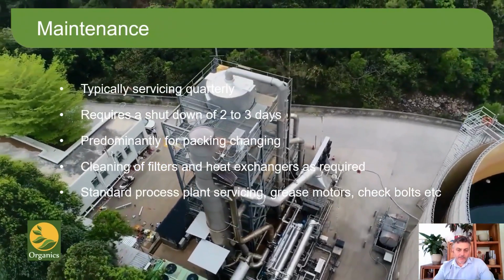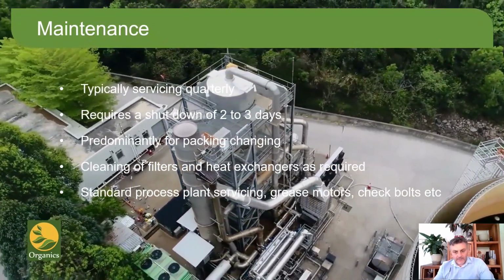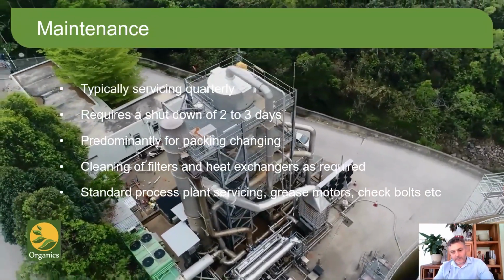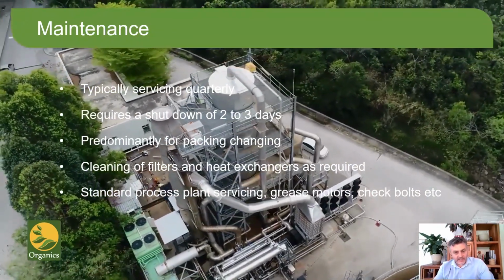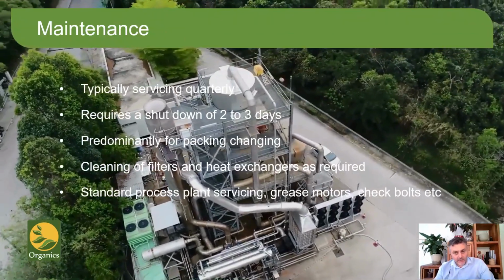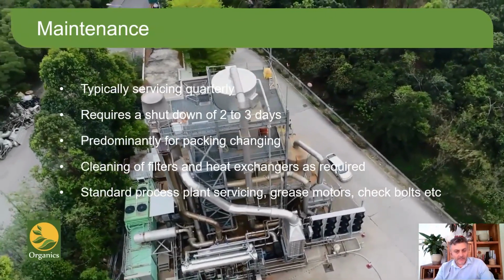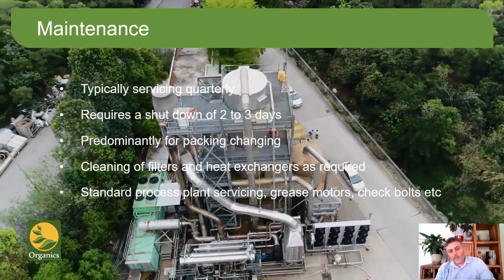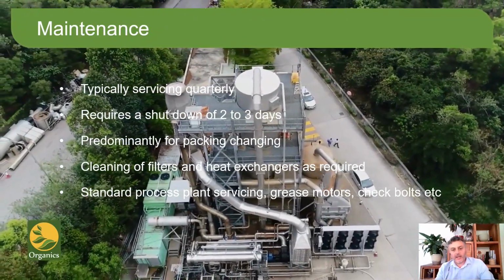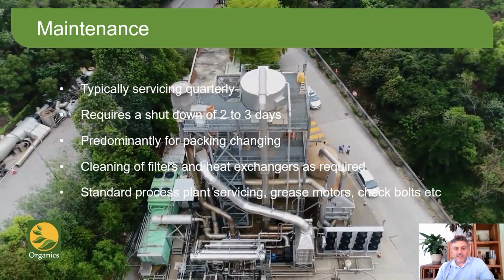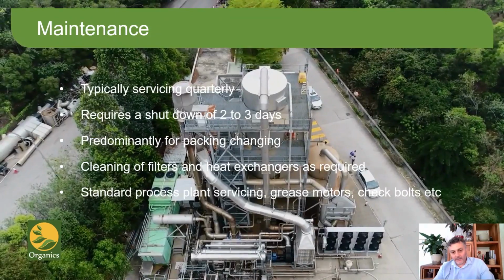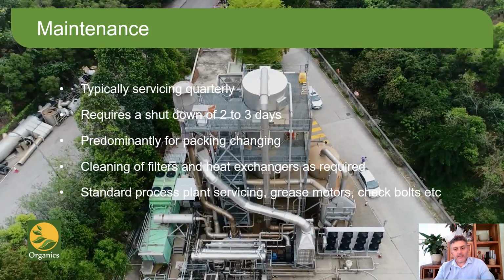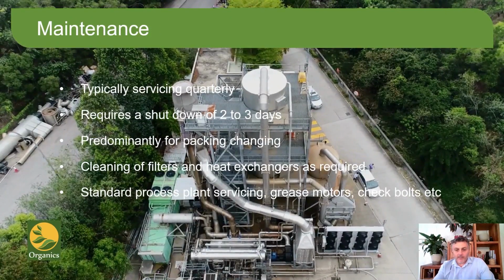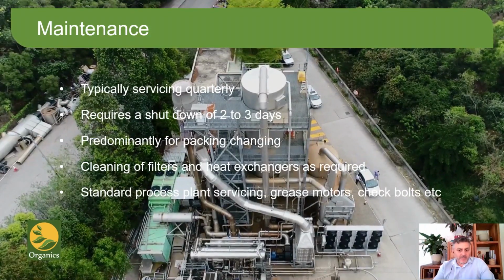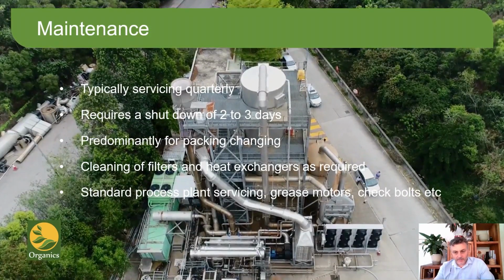Other work involves cleaning filters that protect pumps and cleaning any affected heat exchangers. It is not the case that all heat exchangers need cleaning every service, but most sites identify one exchanger to clean at each shutdown, so that typically the heat exchangers are cleaned about once every 18 months or so. Other tasks in the service are typical of any site plant and include greasing motors, checking belts for tightness, ensuring bolts are tight, and so on.